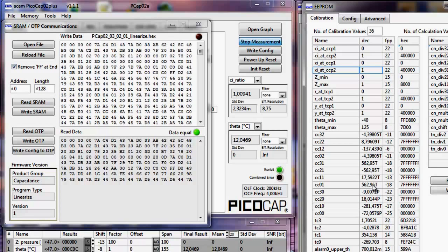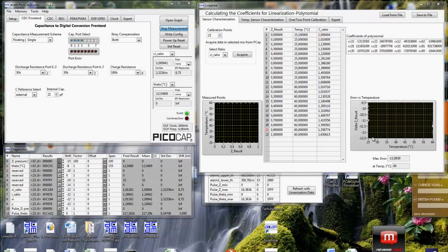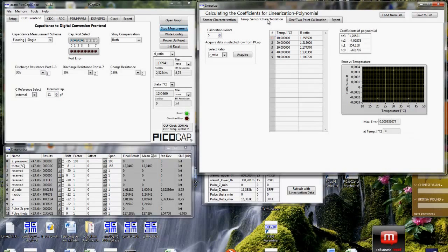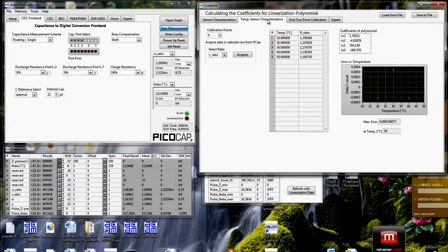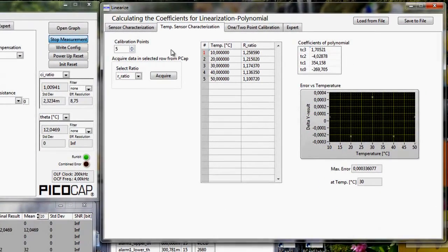If you want to now linearize the temperature sensor on top, I will show you in the next steps how to do that. For the temperature sensor linearization, we go to the next tab here, and actually we have more or less the same page as we had with the sensor characterization, where we can select the number of calibration points for the R ratio.